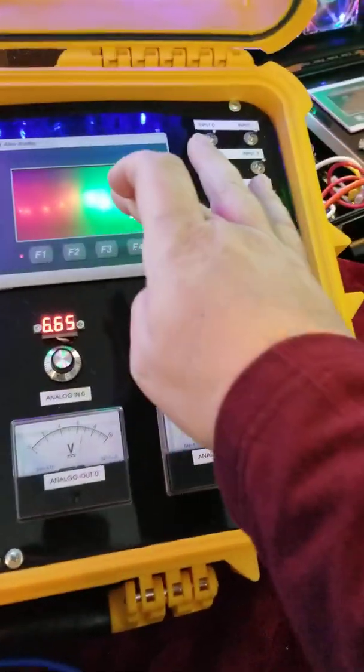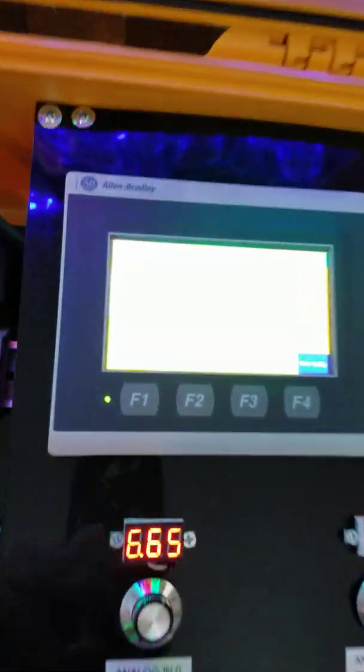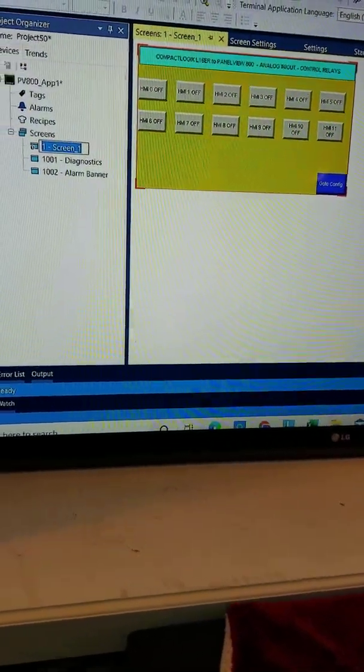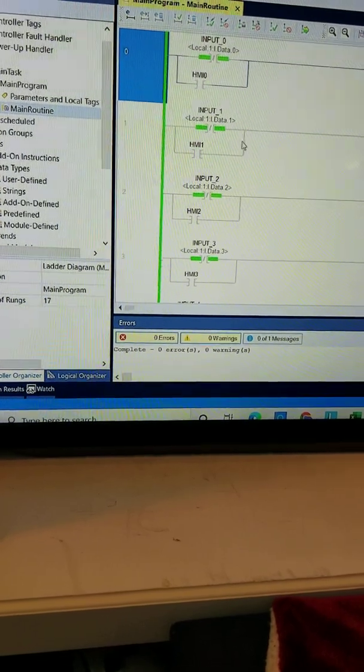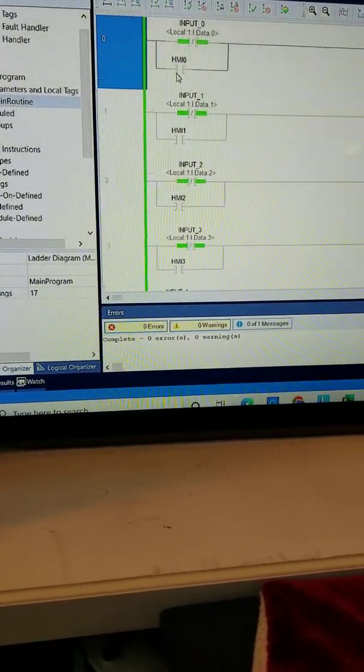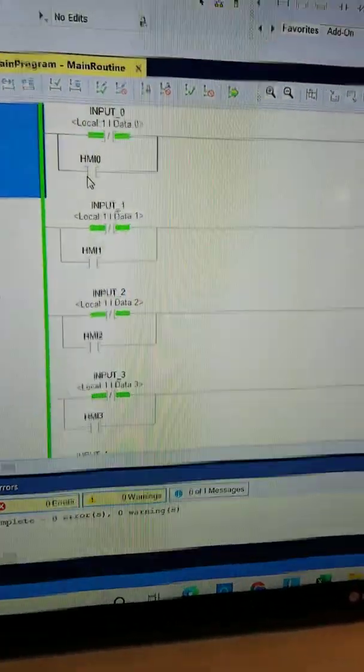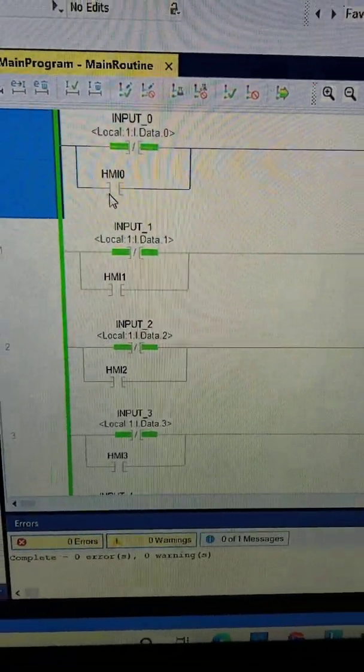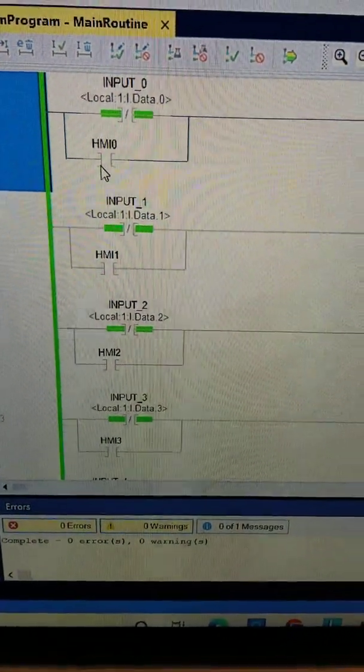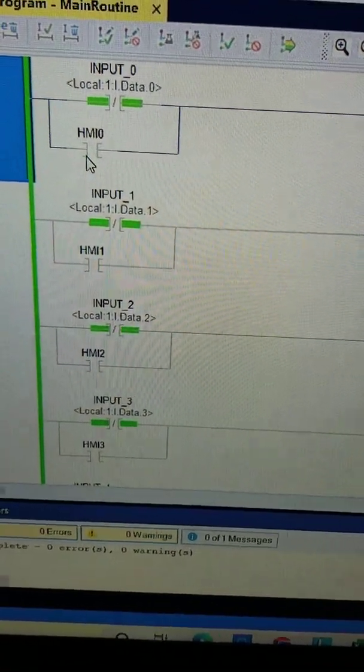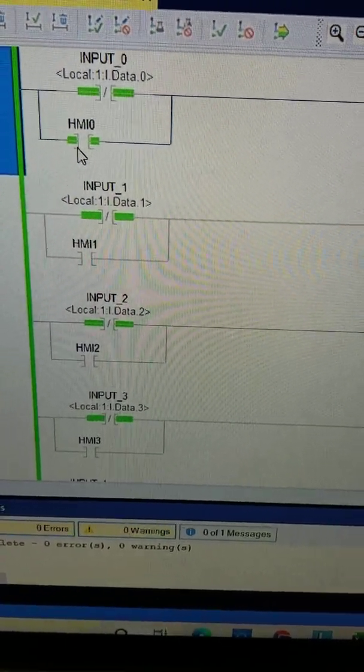So let's do this, let's go to the software. Now we're live on this Panel View and the Panel View itself, if you see that HMI_zero, I'm going to press the HMI_zero here and we can watch it live. Remember the address name is the same, the HMI_zero. It's a bit on the, that we've programmed it to be a bit in the ladder logic. And I'm going to press it here. See how it turned green? It turned green. Now because of input zero is normally closed, the outputs already energized.